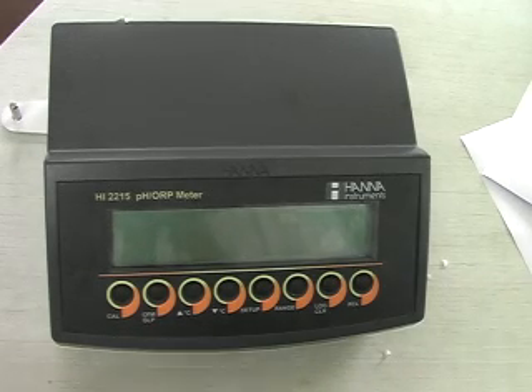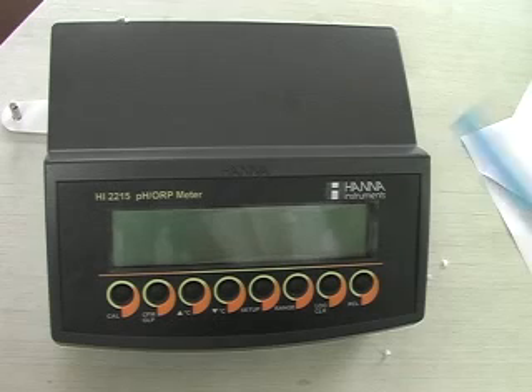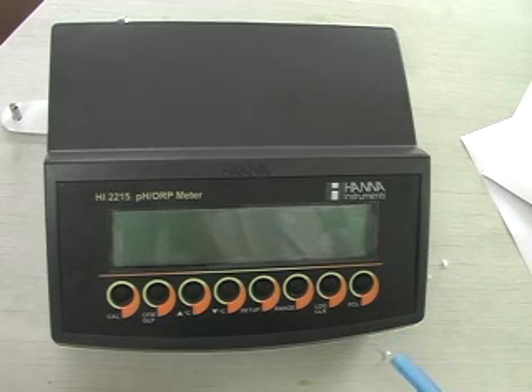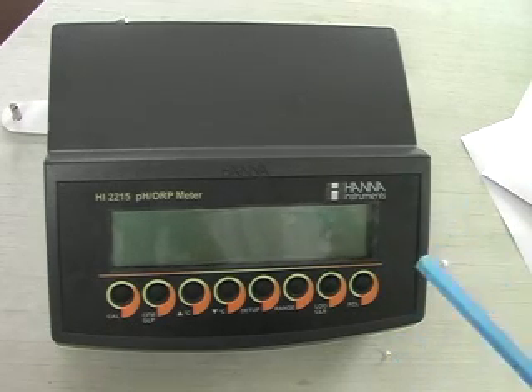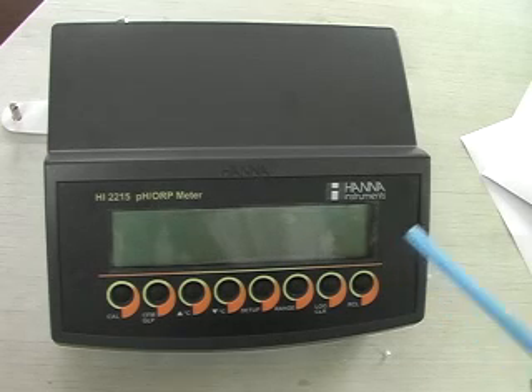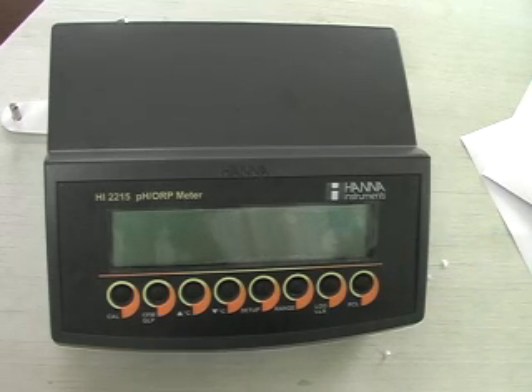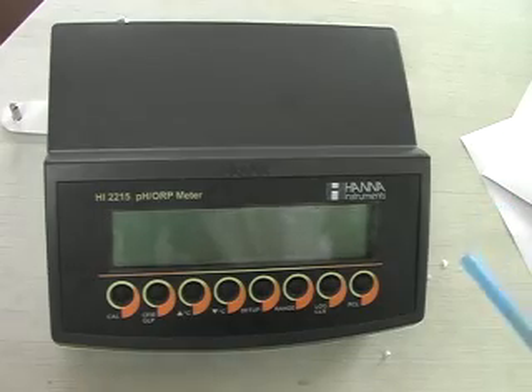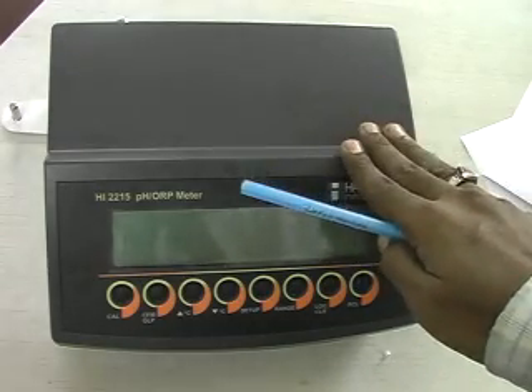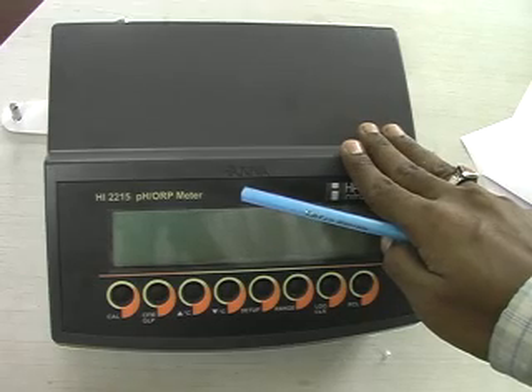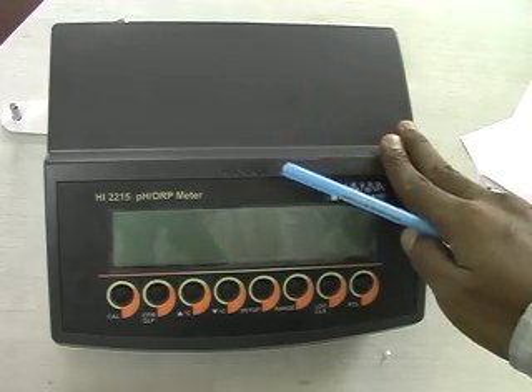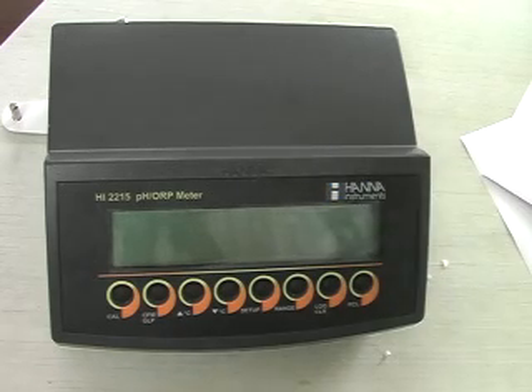It has unique facilities like auto temperature compensation. It has a 5-point calibration, then GLP function. You can store 100 samples into the memory. It has a USB connection for the PC communication. So this is a good meter. Now I will show you the functional description of this meter.